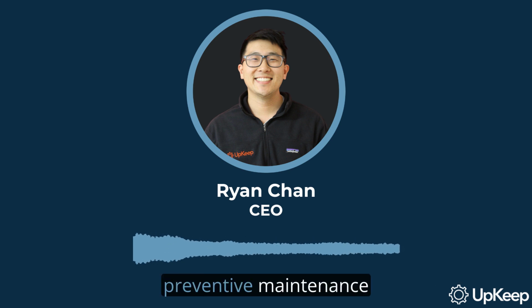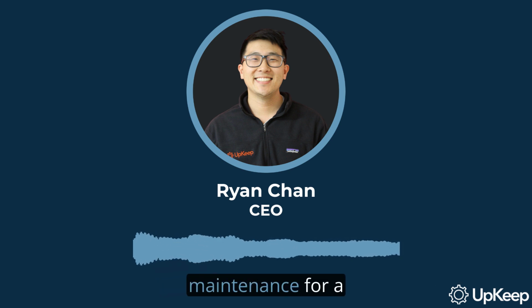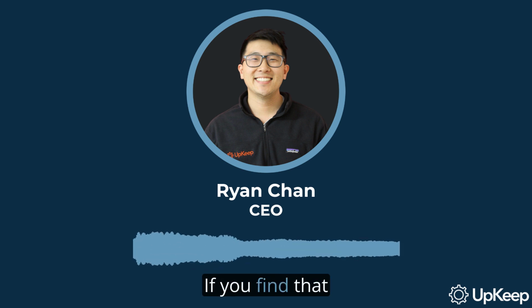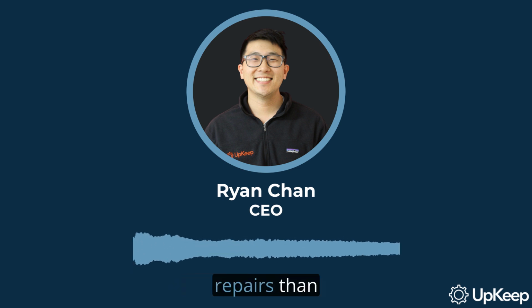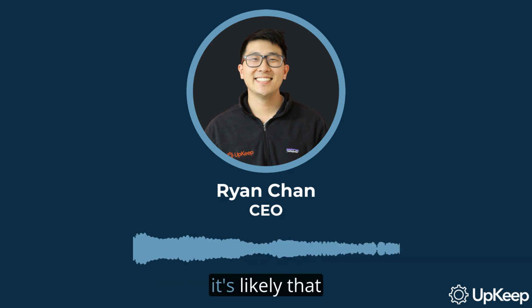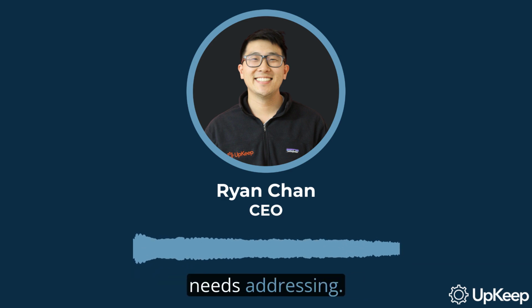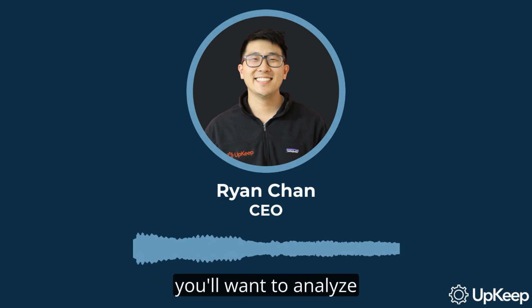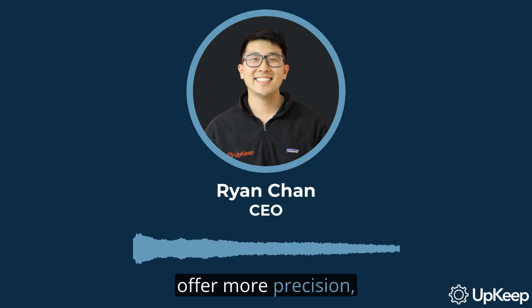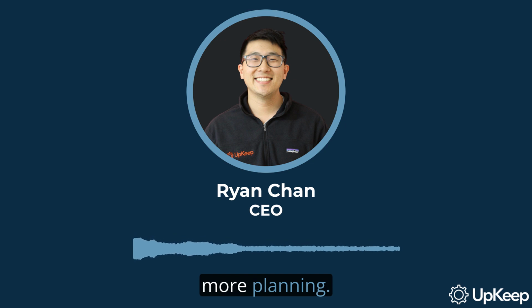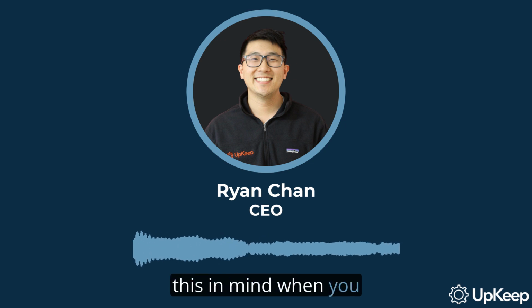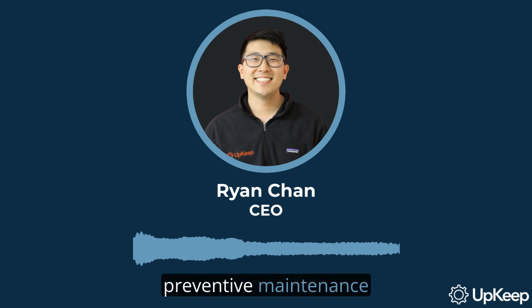Another similar method involves tracking hours spent on preventive maintenance and emergency maintenance for a single asset. If you find that you're spending more time on emergency repairs than preventive maintenance, it's likely that there's a problem that needs addressing. In this case, you'll want to analyze the root cause. These last 2 methods offer more precision, but they do require more planning. So remember to keep this in mind when you start refining your preventive maintenance plan.